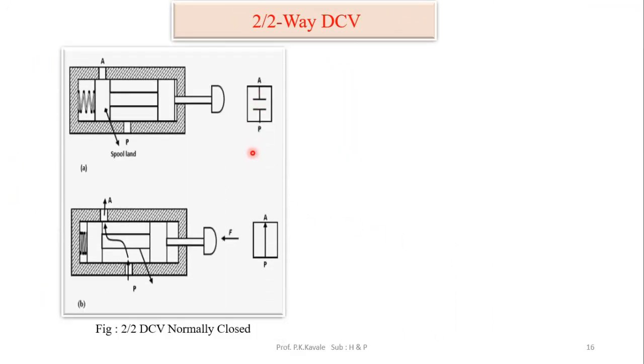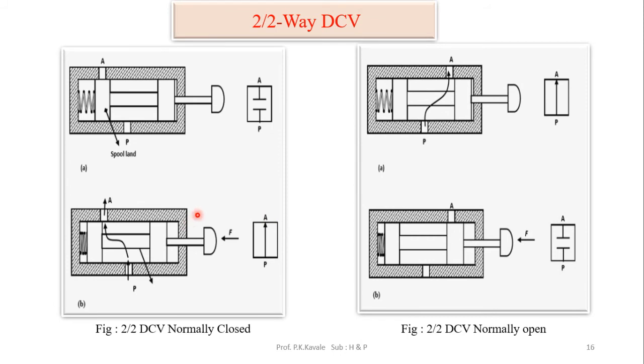A 2/2 DCV has 2 ports and 2 positions. The ports are the pressure port (P) and actuator port (A). In the normally closed position, P and A ports are closed. When pushed, the A port opens and flow diverts from P to A. In the normally open version, during non-operating condition the pressure port and actuator port are connected; to disconnect them, force must be applied.